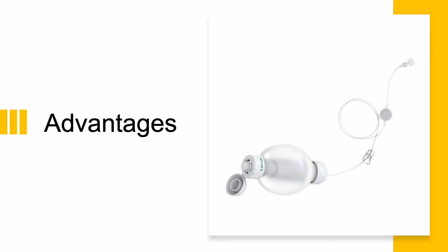The silicone sleeve has the properties of gas permeability, therefore the air entrapment in the silicone sleeve can be diffused out of the pump. Fixed flow rate design does not require programming or drop counting, and transparent balloon construction helps facilitate easier inspection for particulates. Components are not made with natural rubber latex or DEHP.